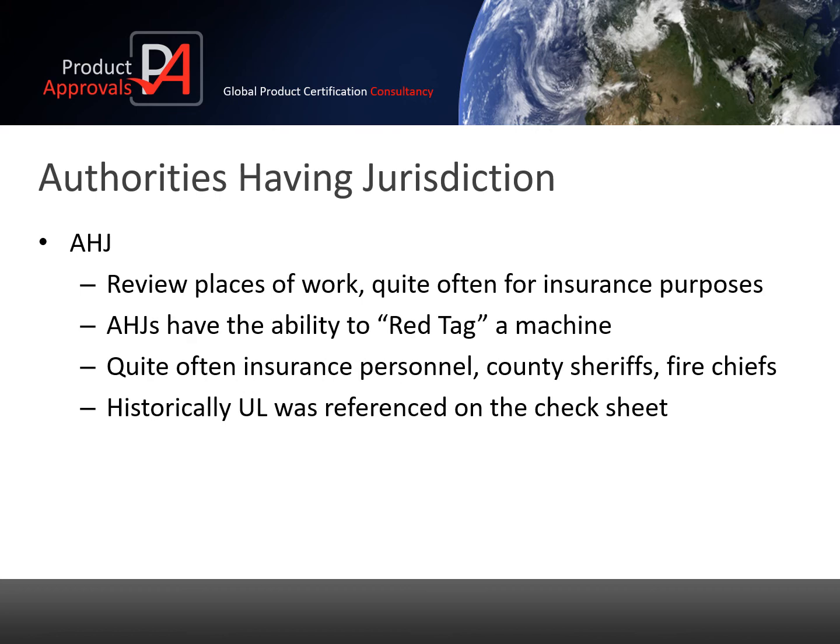AHJs have the ability to red tag the machine, which means if there is something wrong with the machine, it is locked off and power cannot be applied until the issues are resolved. AHJs are regularly county sheriffs and fire chiefs and are not necessarily technical. They regularly use a tick sheet that references UL approval. If no UL approval is in place, then the machine does not get signed off.